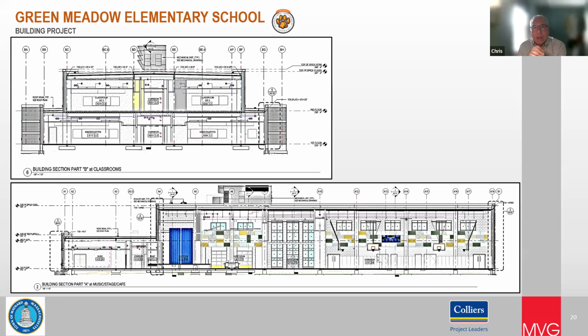A little bit, Ken. You're absolutely right, there's a 4-pipe system in the units to deliver heating or cooling. It's how it gets delivered to individual spaces through the 2-pipe system. Tyler mentioned it well, that even in heating mode, if you're delivering a little more dehumidified air, it's going to feel a little cooler.